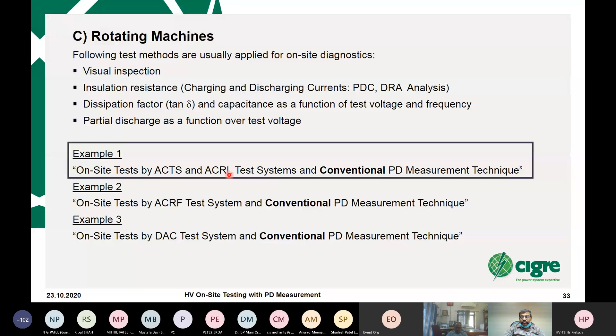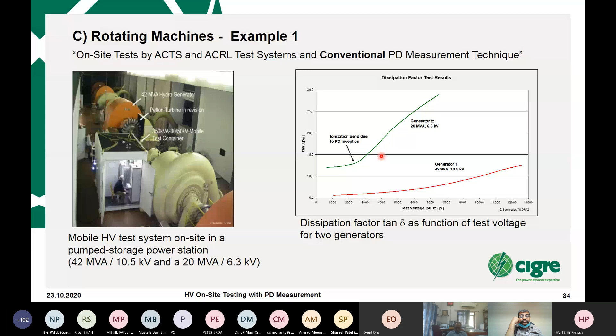This is inside a cavern. It's a water power station, hydropower station, and this is a test device with a test system inside, and it was connected to the machine to test. And the intention was, over the time and the test voltage, if the losses increase, that means you have ohmic losses somewhere due to PD activity or whatever. In this case, everything seems to be fine. And normally you do this test over time. Let's say you have done this test 2 years ago, and now you performed this test yesterday, and maybe last year, 2 years ago, it looks like that, and yesterday it looks like that. That means, okay, something has to be there, and then you need further investigation of this special machine.